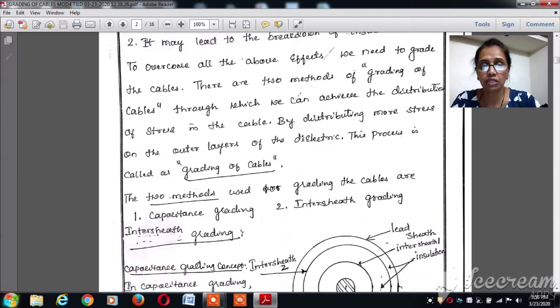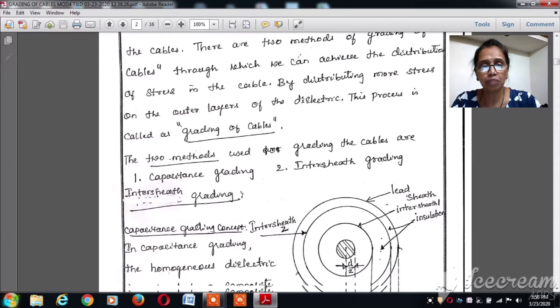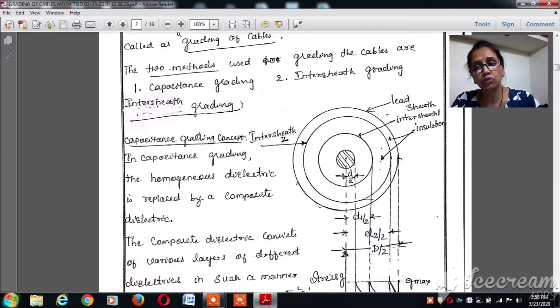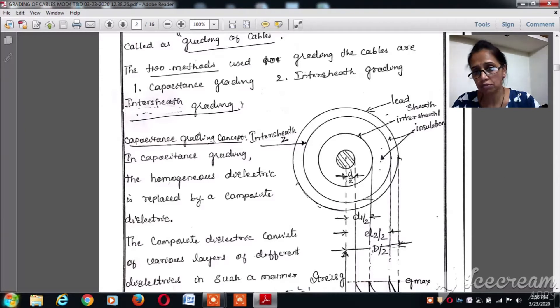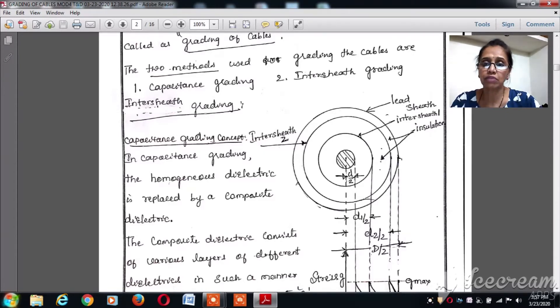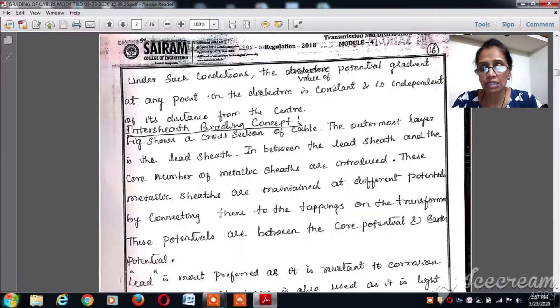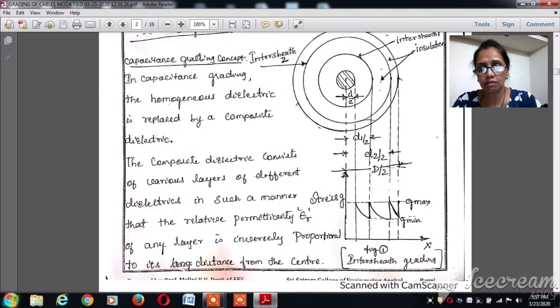By introducing a number of sheets in between, it is possible to achieve uniform stress distribution all over the cable. In capacitance grading, we alter the permittivity by introducing different permittivity materials between the outer surface and the core surface. Instead of maintaining a homogeneous dielectric as in intersheath grading, capacitance grading introduces a composite dielectric to achieve the grading.